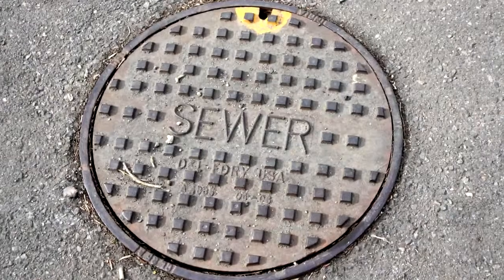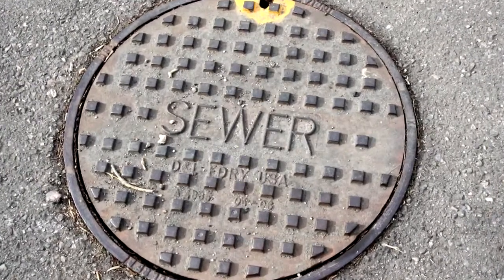I think within the past 4 or 5 years, you've started a program to kind of rehab some of those pipes. Right. We've been very aggressive within the last 4 years addressing I&I, which is inflow and infiltration. Anytime you have a significant rainfall event, pipes do have cracks, manholes do have openings into the sewer system, and that storm water makes its way into our sewer system. Well, when that comes to the treatment plant, we still got to treat it. It overloads it hydraulically, and we run the risk of not meeting our permit limits.